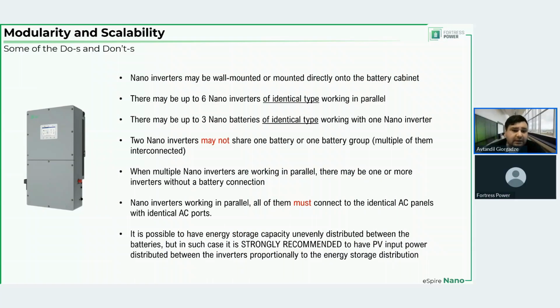Nano inverters working in parallel must connect to the identical AC panels with identical AC ports. So it is not allowed for one inverter to support one electrical panel and for the other inverter to support another electrical panel. At least those two electrical panels must be interconnected. Same applies for the utility side. You cannot have one inverter with one utility transformer and the other inverter with the other utility transformer. Even if you have some inverters with batteries and some inverters without batteries, even the inverters without the batteries must be connected to generator if that generator exists. And that's, by the way, additional point why having the ability of having nano inverter or inverters without the batteries working with the inverters with the batteries.